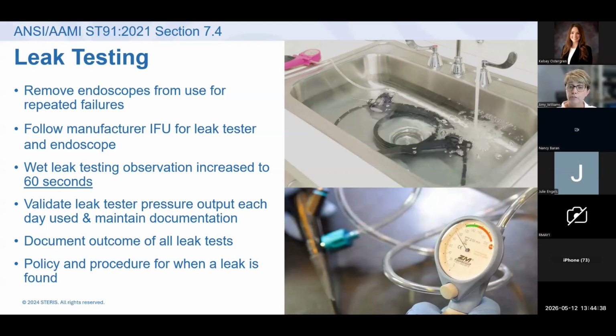What that tells me is there are a lot of people out there who continue to use devices that can't be leak tested or don't leak test at all. So AAMI was very clear with their language here. Okay. They also added a requirement that you should regularly calibrate your leak testers. You should test your testers every day that they're used. So no matter what, if you're doing automated or manual, you should make sure it's properly functioning and that it gives you good, valid pressure outputs. Because if the leak tester is broken, your leak test is worthless. Okay. So you should be testing your testers every day that they're used.